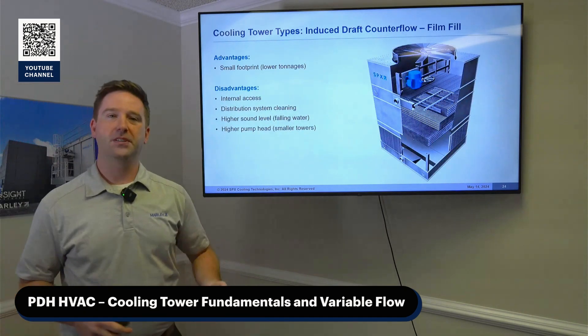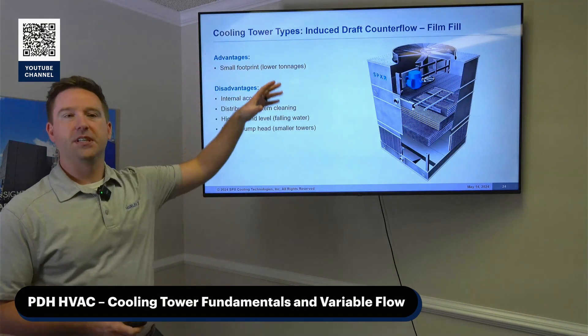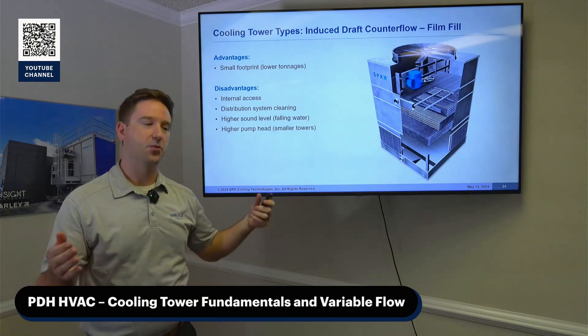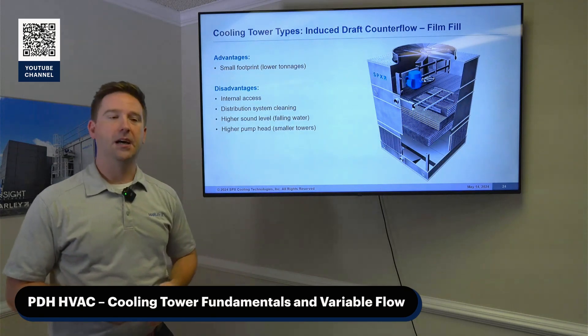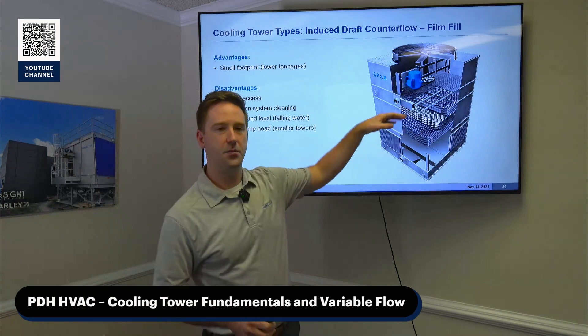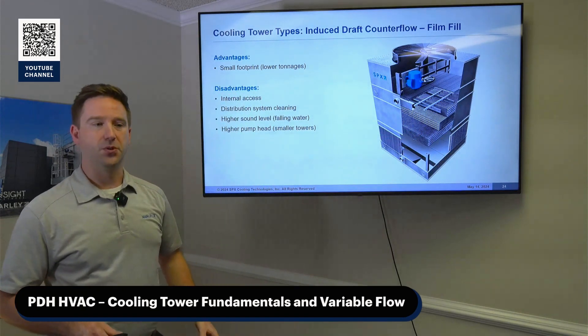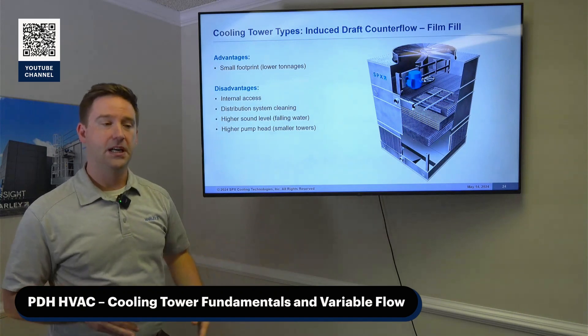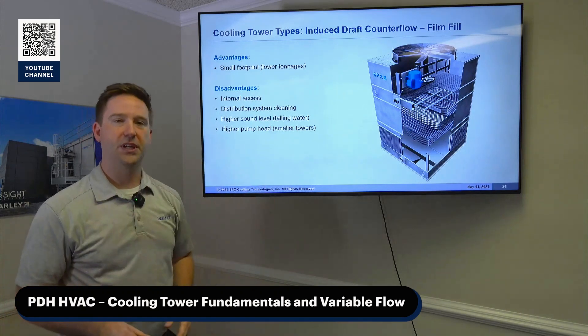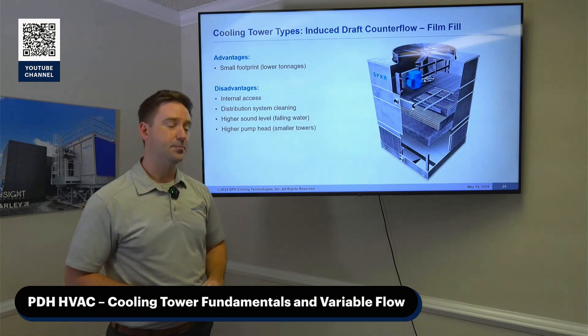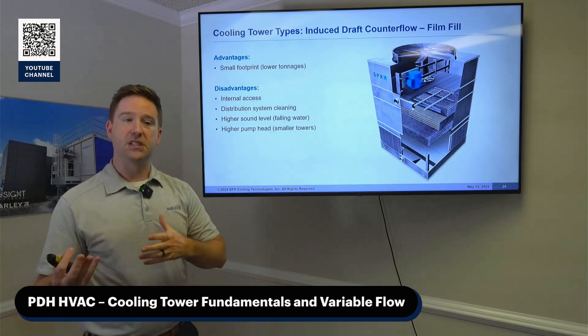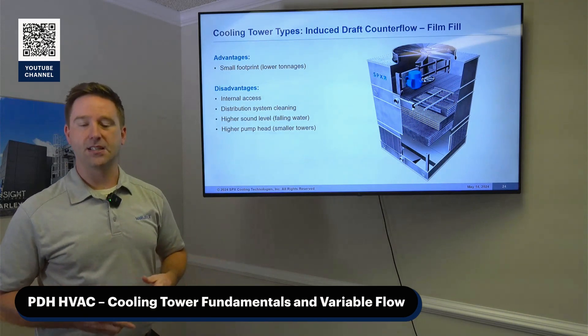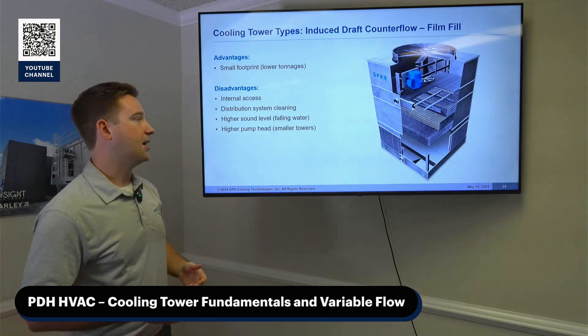Some pros and cons of counter-flow towers: one of the biggest benefits is it was designed to fit into a small space. If you're up on a roof with not a lot of room, it can fit. It has air inlets on all four sides, and under 750 tons it'll have a smaller footprint than the cross-flow tower. You can place one cell in a corner on a building and get the cooling you need. However, because it was designed to be compact, it's not as easy to access the maintenance parts of the tower.